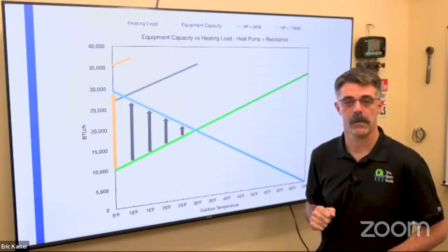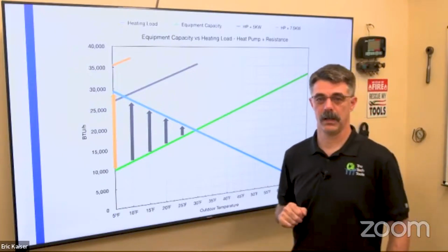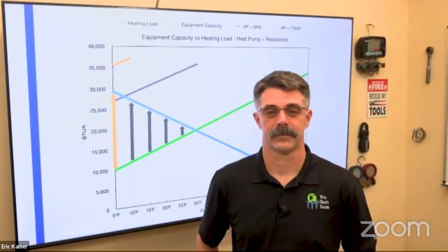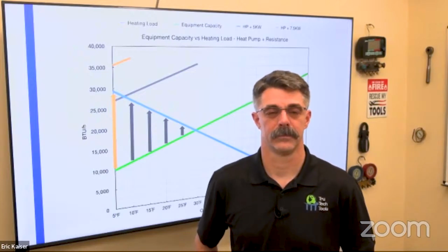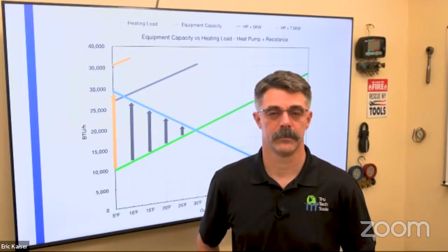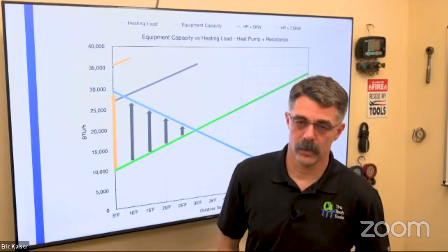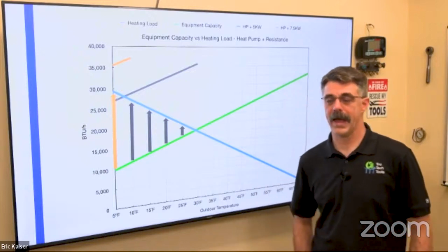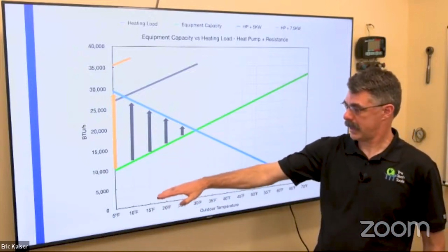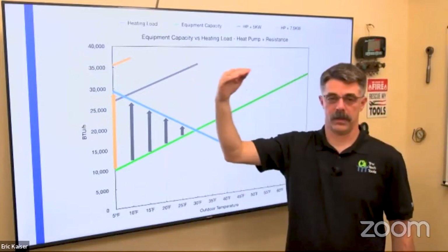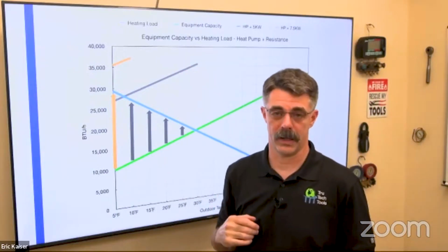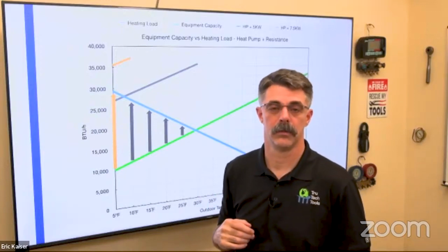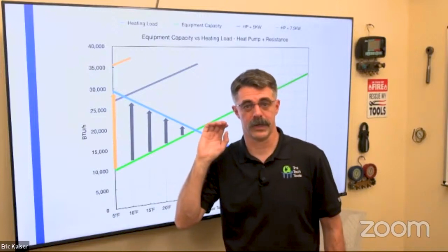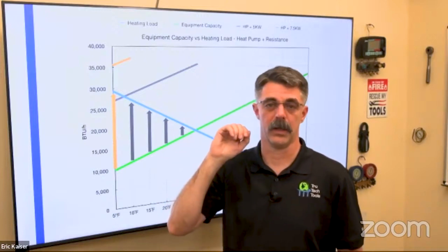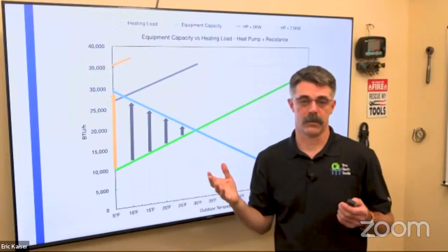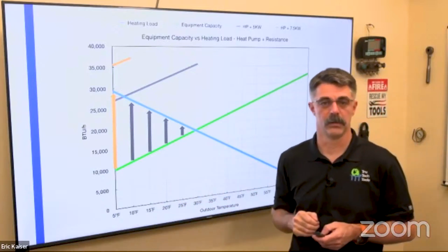Yes, sir. I've got a question. No one's asked it except me. All right. Location. Can you put a coil over strip heat? Does it have to be before strip heat? Might it require reconfiguration of the ductwork? Coils go before strip heat. So when you're additive, just like it is on this graph, we take it up this far with the heat pump, and then we add on with the electric strip heat after it. That's all part of the air handler configuration. So the strip heat is part of the air handler, or is an accessory that goes inside an air handler typically. So not any more reconfiguring of the ductwork than just mounting the air handler in there.